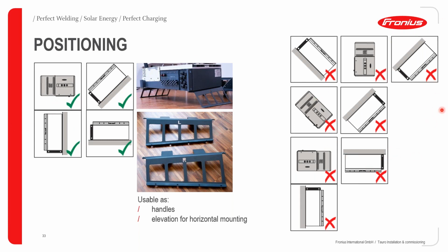None of these combinations are allowed. For example, let's have a look at the first one that isn't allowed. If you look at this setup over here, your weight is centered over here, and you've got a slant which sort of provides greater force due to gravity. And this could lead to a situation where your Tauro could just simply fall off a wall. And if anybody has experienced a grid-tied inverter falling off a wall, you do know if you drop an inverter from 2 or 3 meters, your PC boards will start to shatter, and it could lead to a very costly repair. So please make sure you do take adequate attention to what's allowed and what's not allowed.